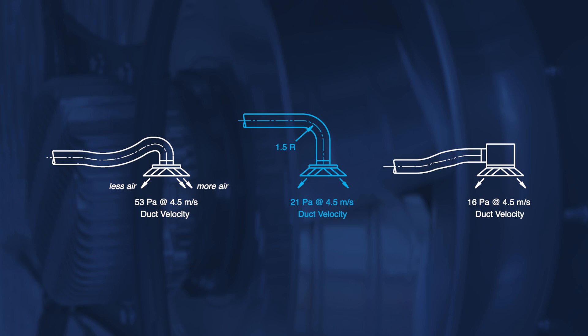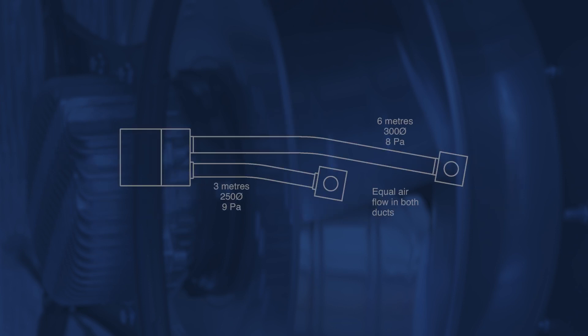Top entry is satisfactory if the flexible duct is supported and makes a gentle radius entry. However, if the flexible duct is left flat and unsupported, it will kink when connected to the diffuser, adding dramatically to the pressure loss. Side entry cushion head boxes are recommended as they improve equal air distribution, reduce noise, and reduce draft.